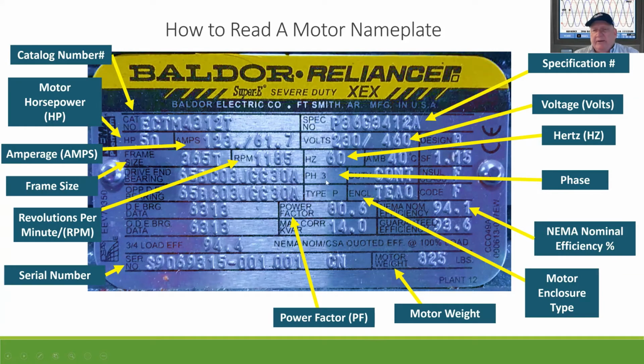Another area you want to look at is the continuous load rating and what the enclosure type is, such as totally enclosed. Then there's the insulation class inside the motor, which is how hot it can operate before it starts deteriorating. Class F is about 155 degrees, which is what the stator winding can get up to without major deterioration. A lot of motors today you can buy with class H, but that's not necessarily the best option, because it just means the motor has higher insulation, but it's going to run really hot.